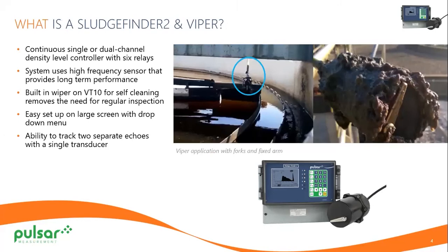What is a Sludge Finder 2 and Viper? Sludge Finder 2 and Viper is a continuous level sensor with 6 relays. It has the ability to track 2 levels or 2 settlement levels on an application, basically 2 inputs. It has a VT10 sensor with a wiper on it. As you can see in the 2 pictures, that wiper is used to keep the sensor face clean from buildup.